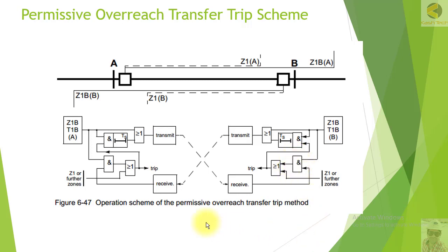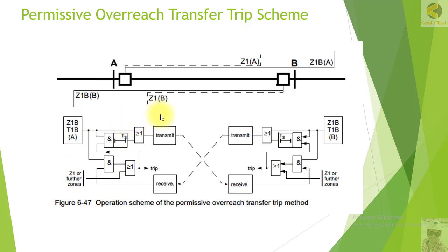It also needs a permissive signal at the remote end. When the permissive signal is available — for example, the relay at the remote end has also seen a fault in the forward direction — then both inputs are 1, this is an AND case, and the relay will give a tripping command. Alternatively, if the relay picks up in zone 1 it gives immediate tripping, or if it picks up in Z1B and also receives a remote signal it will trip. This is how the permissive overreach transfer trip scheme works for station A and station B.